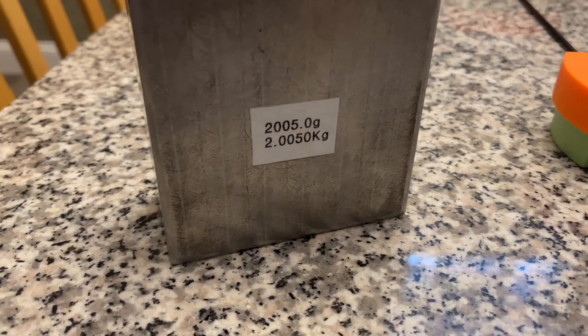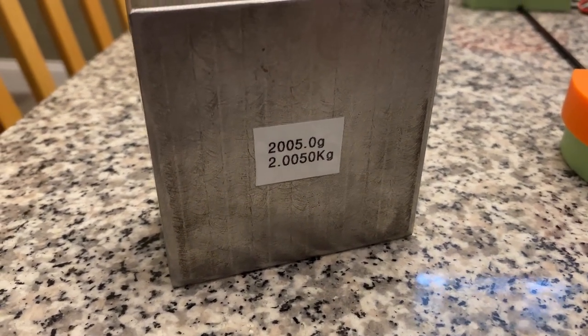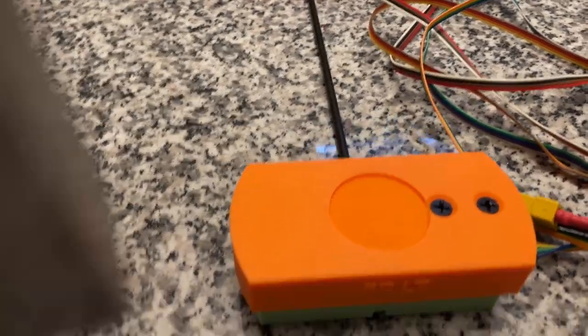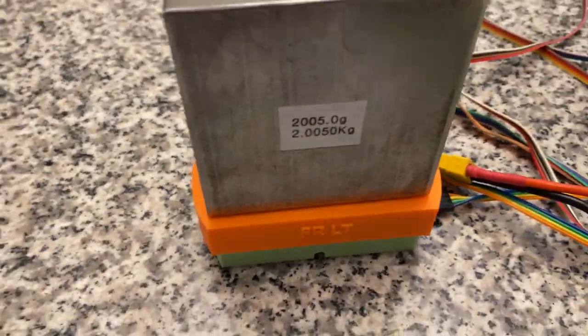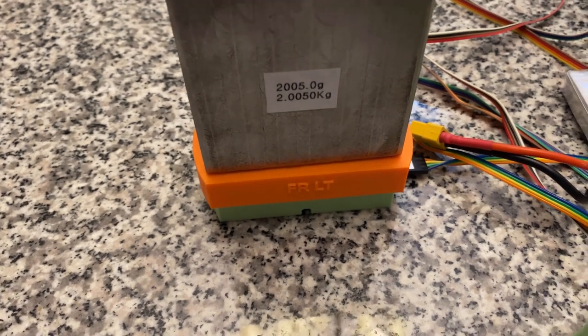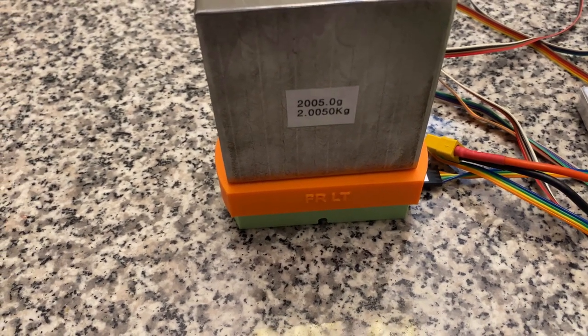For calibration, I just use a block of steel. It's 2005 grams, and we just set that on top of the load cell and calibrate it. I'll show you the calibration sequence.